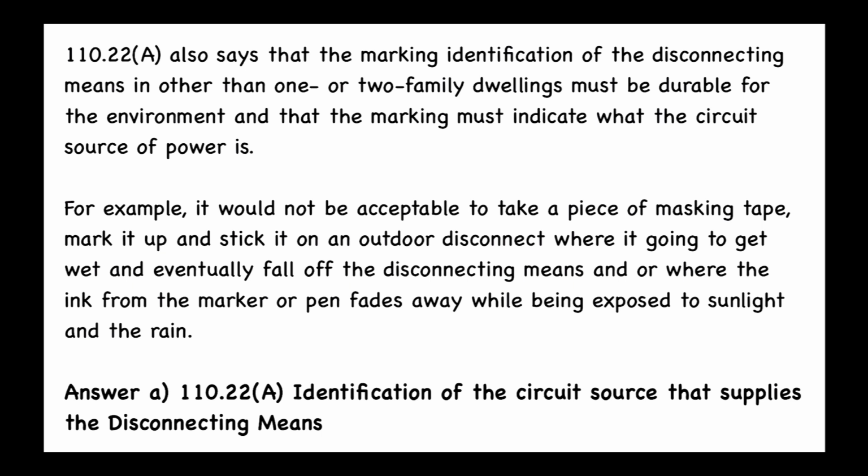And it's also good practice, whether that disconnecting means is evident or not evident, to mark it right on the disconnecting means. This is what the disconnecting means is for: it's for this motor. And then you also mark what the source of the power is, the panel number and the circuit breaker number. It's just good practice. All right, let's continue back in our textbook.